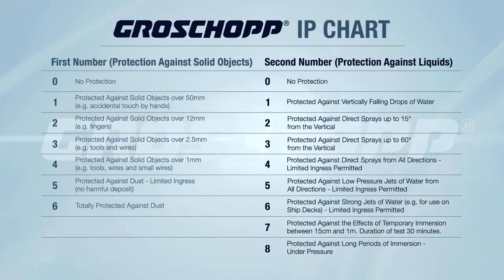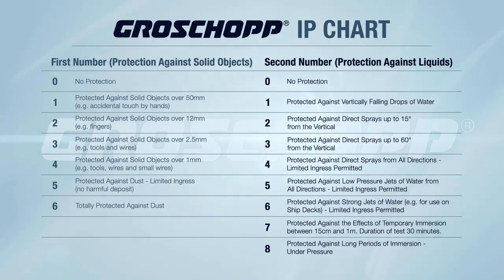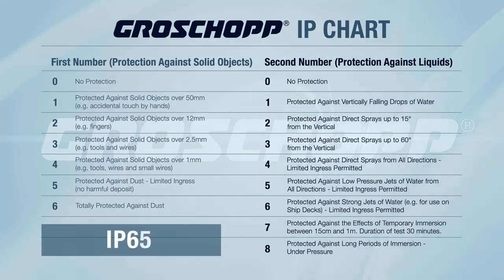We have two reference tools to help you with these environmental specifications. The first is our ingress protection chart, or IP for short — we've included a link to it in the description. IP ratings are used to provide an industry-wide understanding of a motor's protection against dust and water. For example, a motor rated IP 65 would be considered dust-tight and splash-proof.